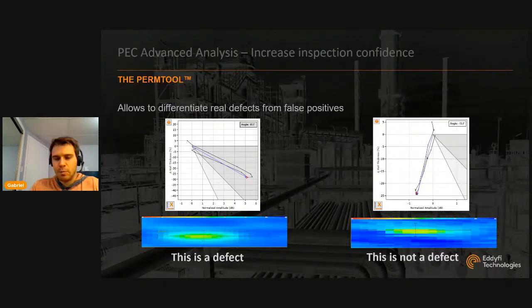The key benefit and the key breakthrough with that tool is that it enables users, technicians, PEC data analysts to make the difference between a real defect and a false positive. So over time, PEC has been prone to false positives in some cases. With experience, you can manage them most of the time, but it's not always that intuitive. So we built a very intuitive tool that will show a different signature when you're putting your cursor over a real indication with wall loss as compared to a false positive like this one. This is suspected to be a hard spot, so that was a bare pipe, no insulation, no wall loss measured with UT, but when you scan with PEC, and you could get the same thing with different electromagnetic techniques, you're seeing a change in properties. So there's a change in conductivity or permeability that's affecting the PEC sizing. But with the PERM tool, we're showing a different signature.